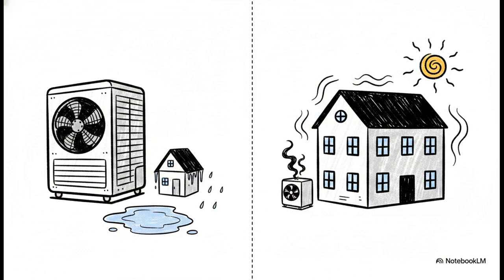On the left, we see oversized systems. Because they're way too powerful, they short cycle. They blast a ton of cold air, shut off way too fast, and actually completely fail to dehumidify the space. That leaves your house feeling cold but incredibly clammy, all while wasting massive amounts of energy. On the right, undersized systems have the exact opposite problem. They run constantly, desperately struggling to heat or cool the space, leading directly to rapid mechanical failure. To get it right, you can't just guess. You need precise mathematical load calculations.